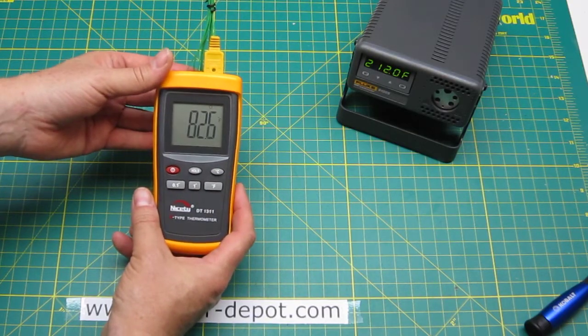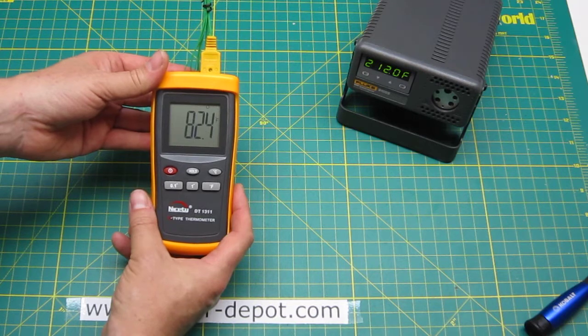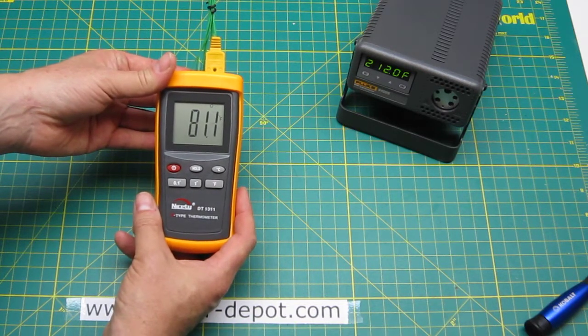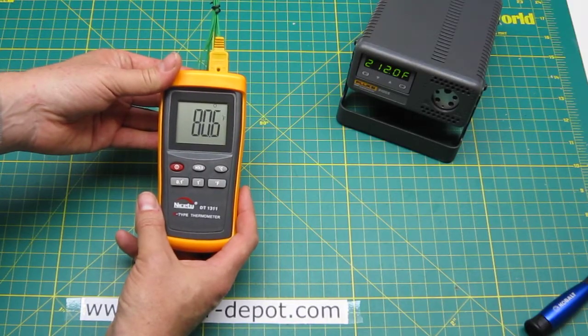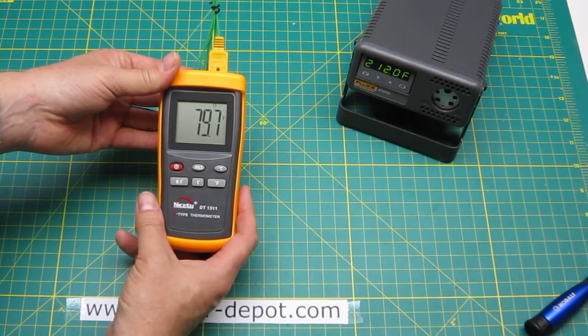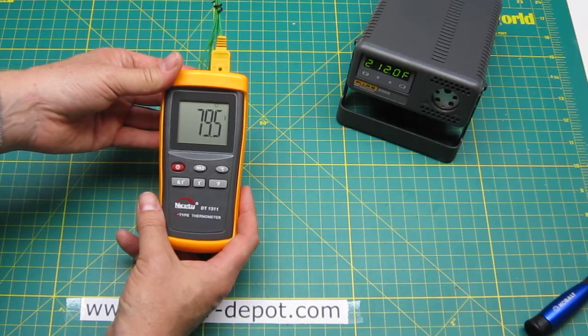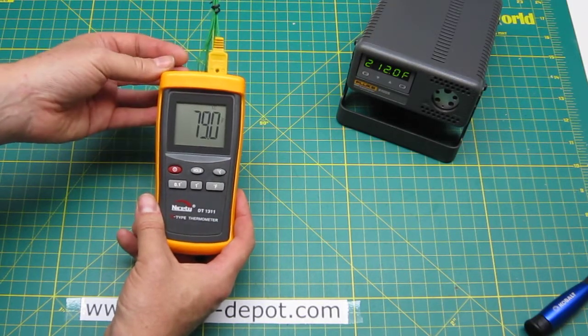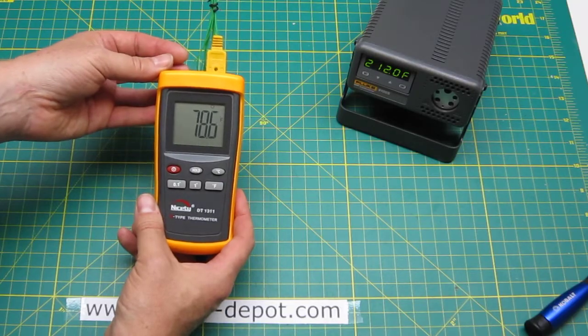The great thing about this meter is that it is a full-scale K-type thermometer. That means it can measure as low as minus 328 degrees Fahrenheit and up to 2498 degrees Fahrenheit and that's the full range that a K-type thermocouple can do.